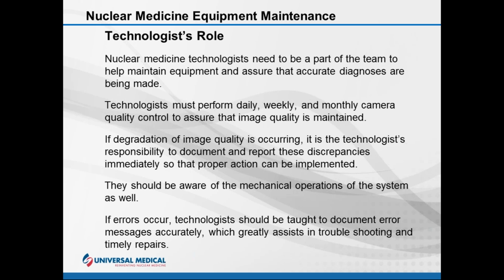If image quality degradation occurs, it is their role and responsibility to document and report these discrepancies as soon as possible so that you can take action. For the mechanical operations, they should be aware of grinding noises so that they can inform you about it to repair it. And if an error occurs, technologists should be coached and taught to document these messages so that you can do accurate troubleshooting.